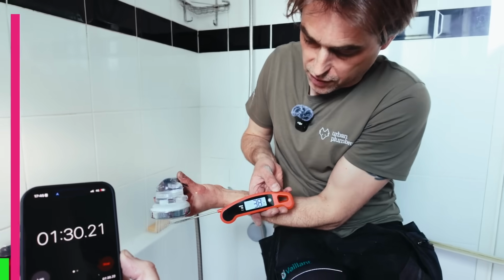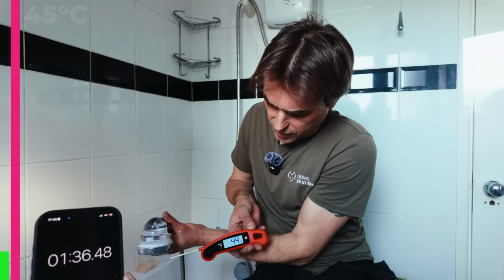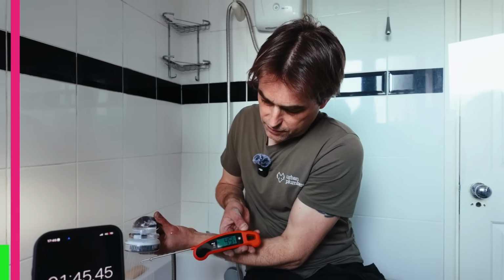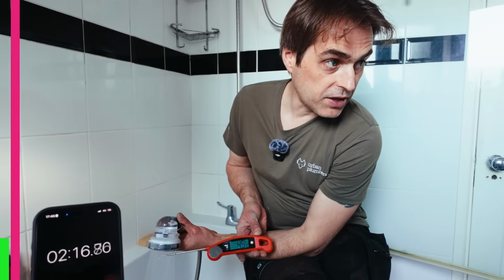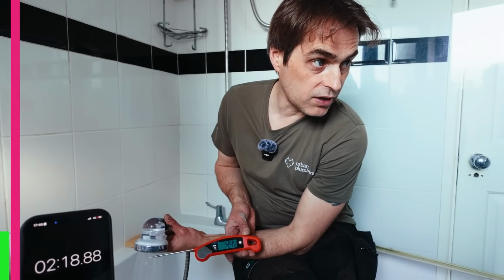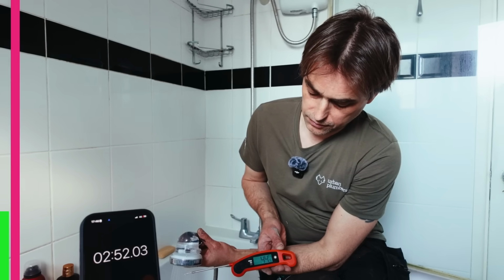43, 44, 45, that's getting a bit hotter than I wanted. That's hotter than anyone would shower typically. The heat pump hasn't kicked in. Oh, I think it might just kick in. Yeah, 2 minutes before heat pump kicks in to support it, yep. I mean, is 45 degrees showering temperature? Yeah, it's too hot. It's too hot for showering. You can't put your finger in it. You should be at 41 or something.